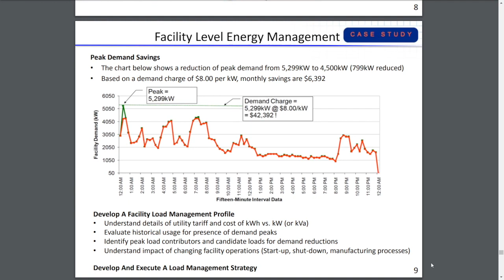Okay, and just to give some examples of what facilities do with the data. Before working at Groom, I had worked at a company that did demand reduction projects. So we went to industrials, we reviewed tariffs, we looked at usage profiles, and this is what we would typically find. What's showing there is an example of kilowatts over time, and this was a facility that had electric arc furnaces melting steel. So 3 furnaces ran in 30-minute cycles, and just like the aligning of the planets, once in a while they would all hit at the same time, and suddenly you're at your 15-minute peak for the month.